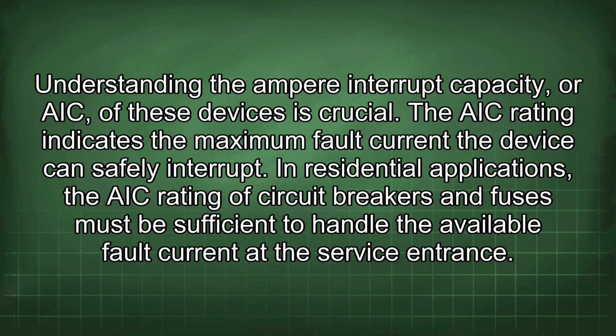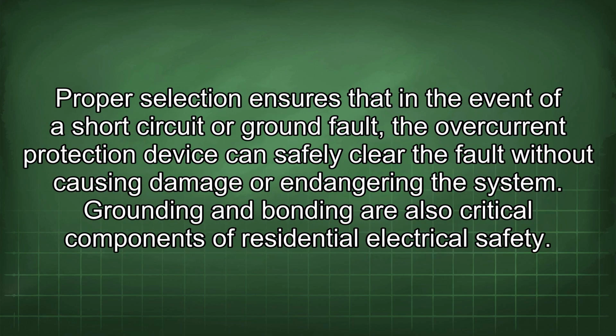In residential applications, the AIC rating of circuit breakers and fuses must be sufficient to handle the available fault current at the service entrance. Proper selection ensures that in the event of a short circuit or ground fault, the overcurrent protection device can safely clear the fault without causing damage or endangering the system.